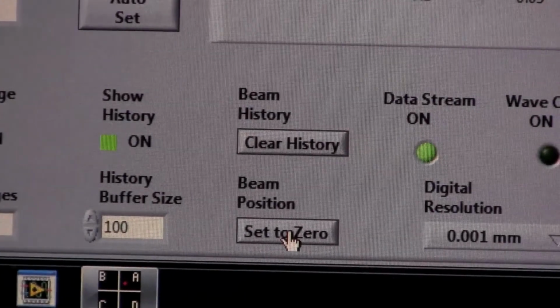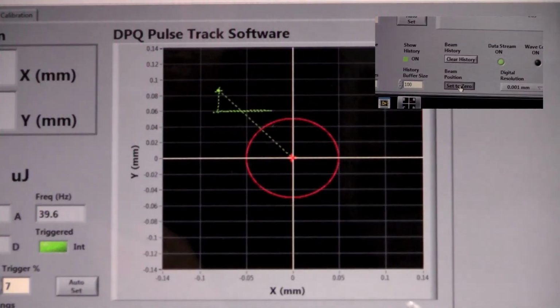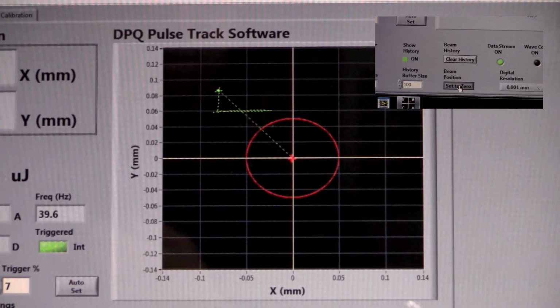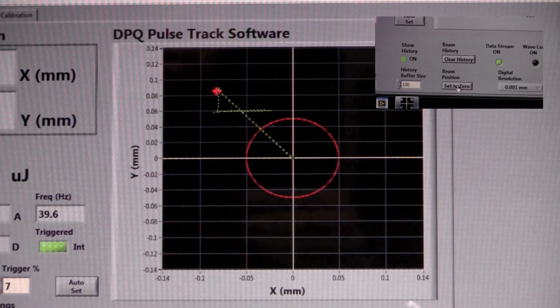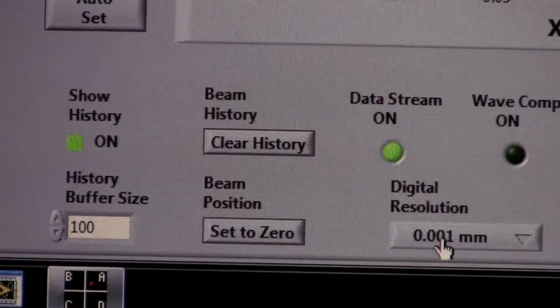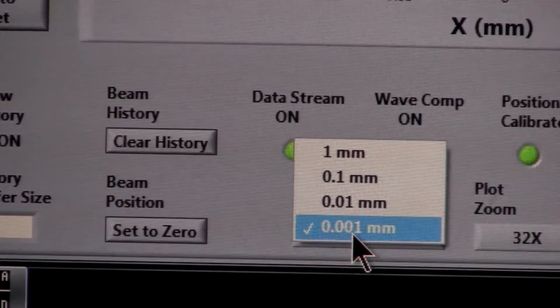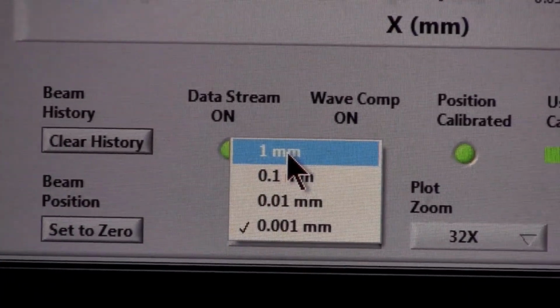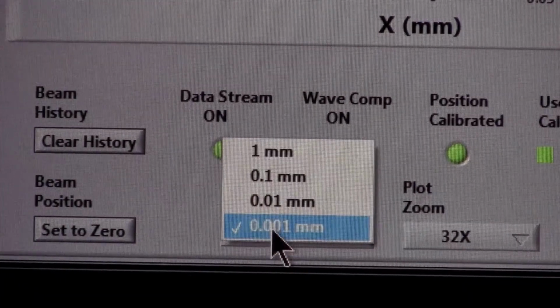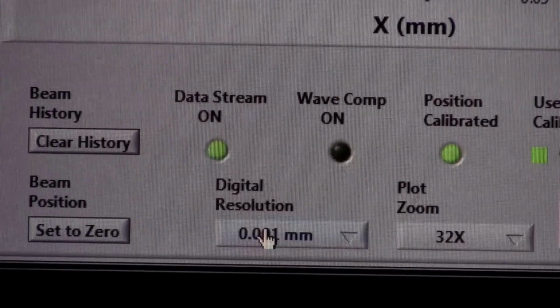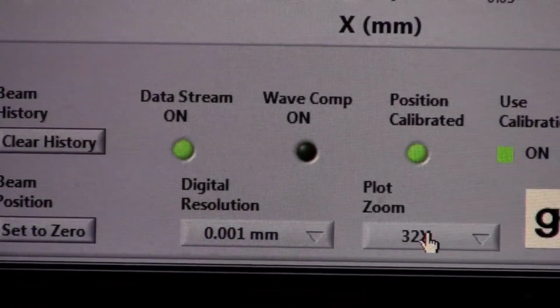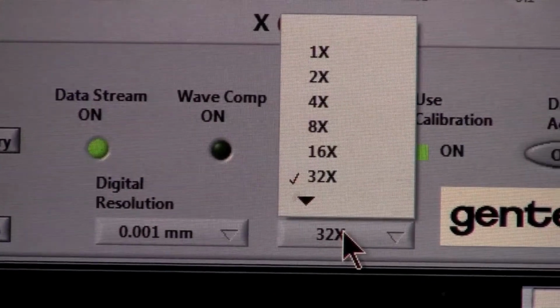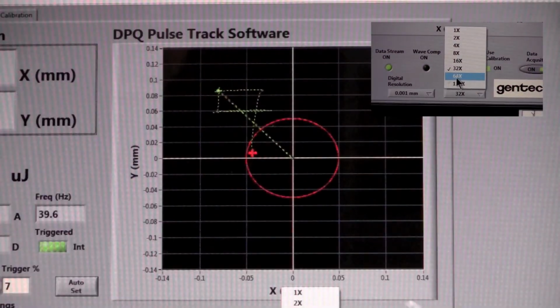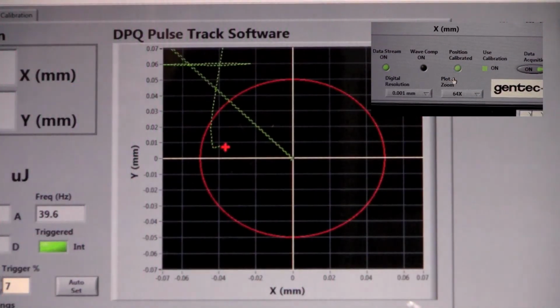Set to 0 lets you set an electronic 0 once you're near a physical 0. It's quite handy for basic alignment applications. You can set the digital position resolution from 1 millimeter to 1 micron. You select from a pop-up menu. We have set it to the highest resolution. When you're trying to center the beam, you'll find the plot zoom very handy.